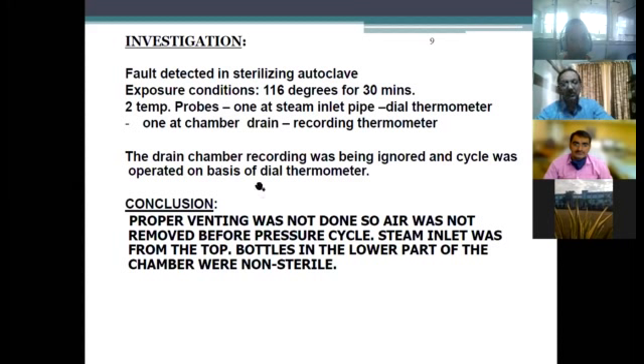If they would have checked the drain chamber recording of the thermometer, then that would have shown less temperature than 116. And as a result, the batch should have failed at that point, but they had ignored that, and as a result, this problem had taken place.